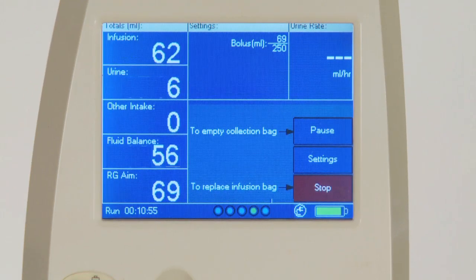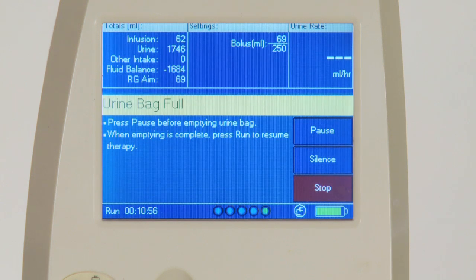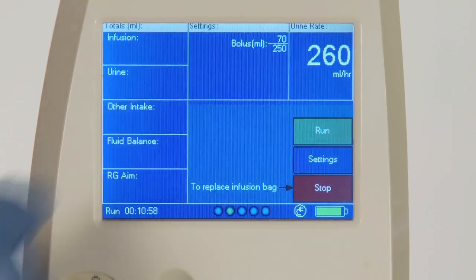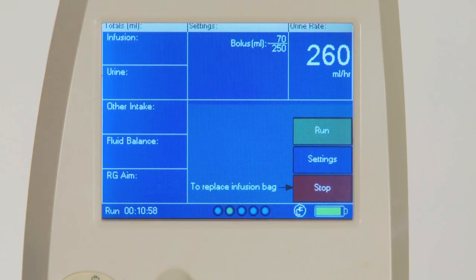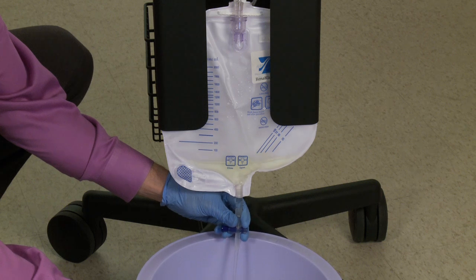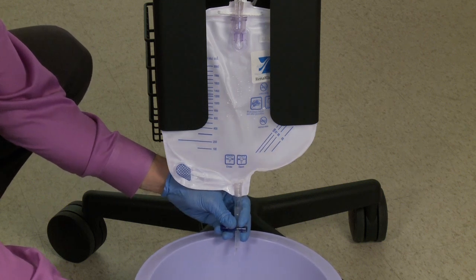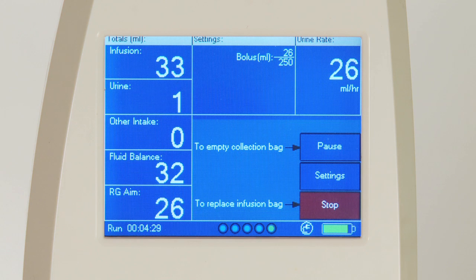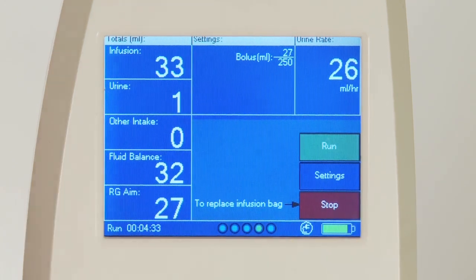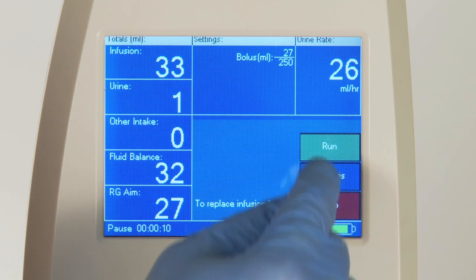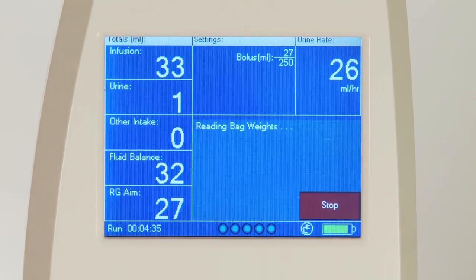The urine collection bag should only be emptied during the pause mode. Pause mode can be entered either after the urine bag full alert has been displayed or any time during operation. If the urine bag full alert occurs, press Pause, empty the collection bag. During operation, make sure the console is in run mode. Press the Pause button, empty the collection bag, and press the Run button to resume the therapy.